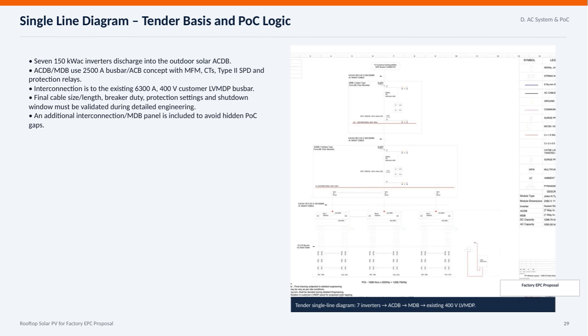It's important to note that final details like cable sizing, breaker duties, protection settings, and shutdown windows will be carefully validated during detailed engineering to ensure reliability and safety. Additionally, an extra MDB panel is included to address any potential gaps at the point of connection, ensuring seamless integration of the solar system into the factory's electrical infrastructure.